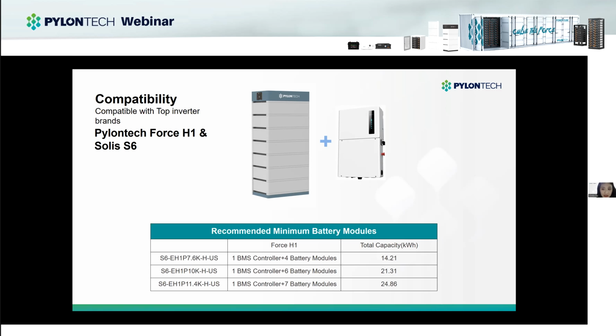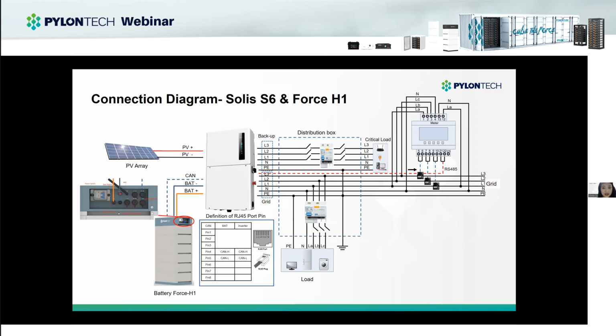And this diagram is the connection diagram for the Solis S6 series and the Force H1 series. From the DC side, the PV connects to the inverter, and the battery also connects to the inverter. There is a pair of power cables connecting the battery to the inverter. Then the Solis uses CAN communication, so you should connect the CAN port to the inverter. From the AC side, the inverter connects to the load and the grid.